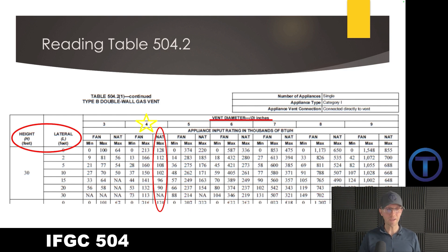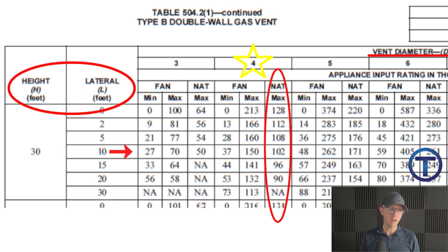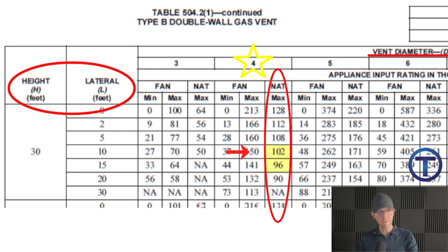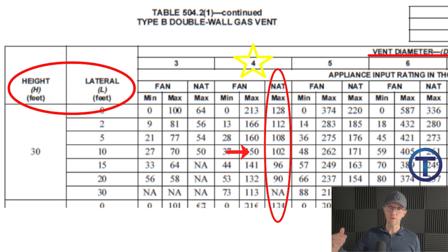You'd have to know the appliance that's being connected. If you have multiple appliances, then you would total those BTUs and use that as your number, and you come across and find where it fits. As with all tables, let's say I have 100 BTUs — on this table we've got 96 and then it goes up to 102. I wouldn't use the 96 line; I'd go to the 102. So we're looking for equal to or greater than. Does that make sense? Let's give it a try — let's do a practice problem together.